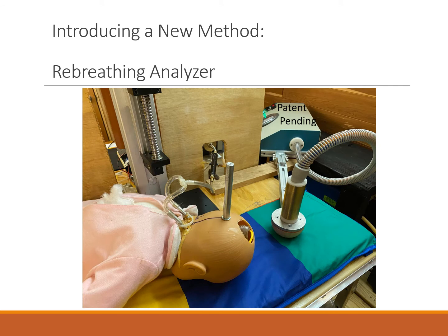Sometime in 2019, I began development of a new kind of measurement tool to evaluate rebreathing. Rather than using carbon dioxide as a tracer gas, the new rebreathing analyzer uses warm air and very sensitive temperature measurements. The configuration shown here uses a hemisphere probe on an articulating arm. In this photo, both types of methodologies are used side by side for comparison.